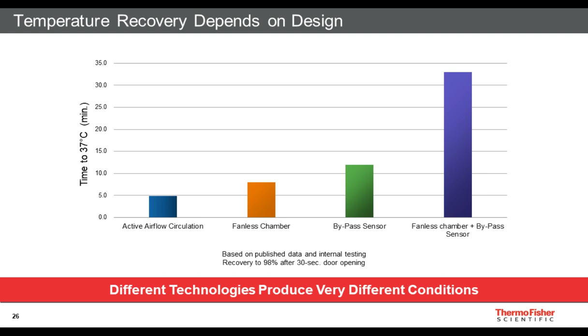Going left to right, the yellow bar shows recovery from a 30-second door opening to 37 degrees Celsius in an incubator without a circulating fan. And you can see that recovery is a little bit slower. If you put the temperature sensor in what's called a bypass location, and I'm going to talk about bypass sensors later in the talk, but essentially it's outside the incubator chamber, that slows the recovery even further, so that's more than 10 minutes to recover to 37 degrees after a 30-second door opening. And then the last bar shows you more than a 30-minute recovery time for an incubator without a circulating fan and with a bypass temperature probe. So my point here is that even though incubators generally look very similar from the outside, different technologies, so different design and engineering that goes into those incubators, can produce very different conditions for cells.